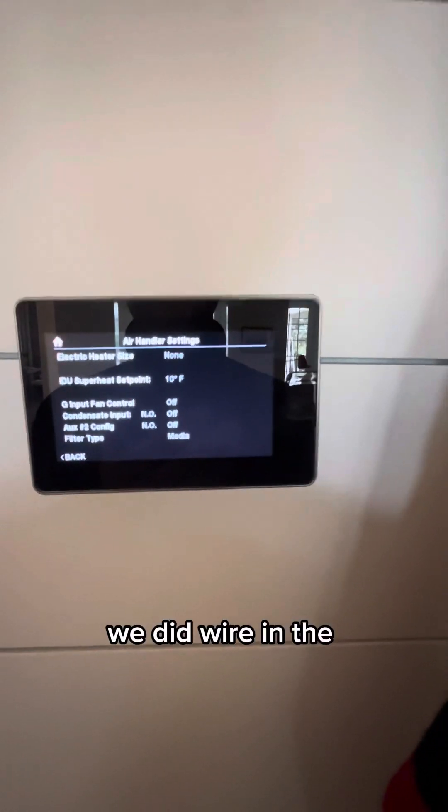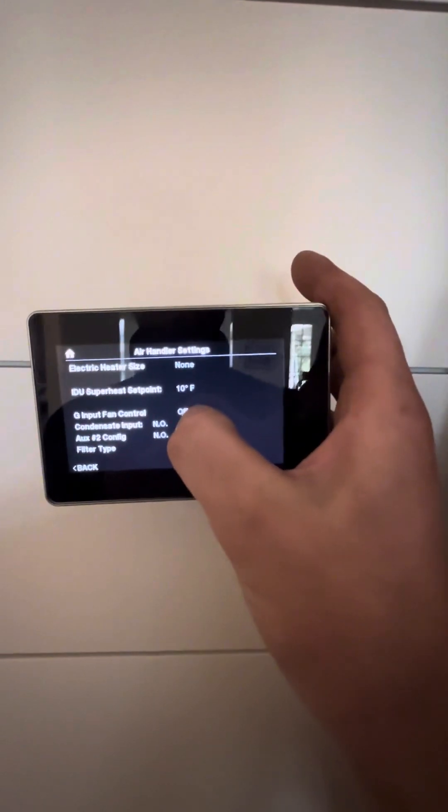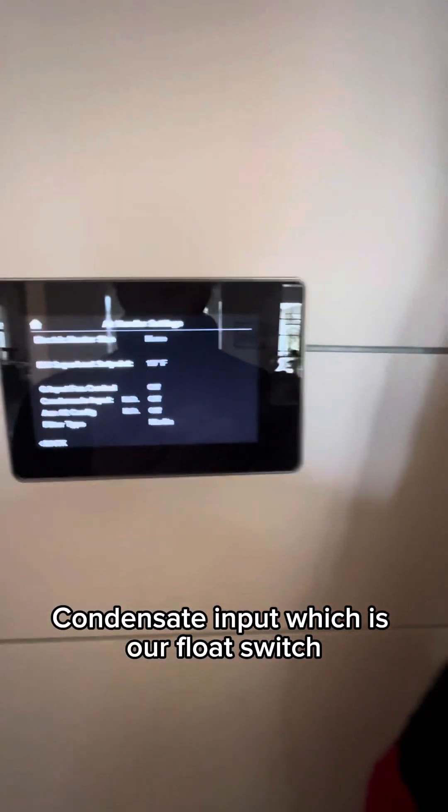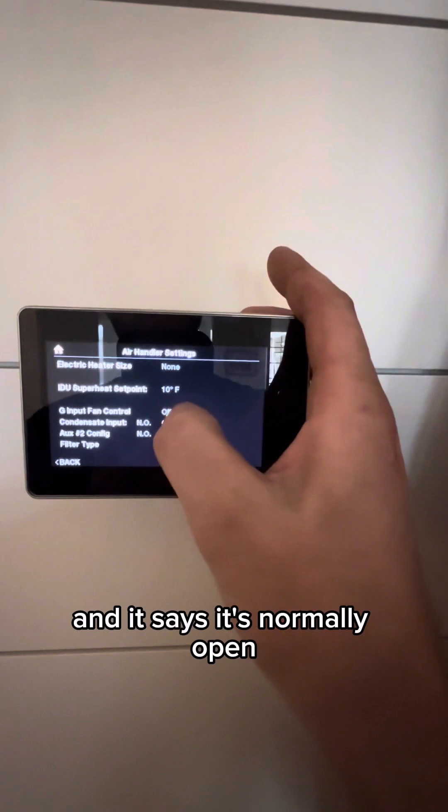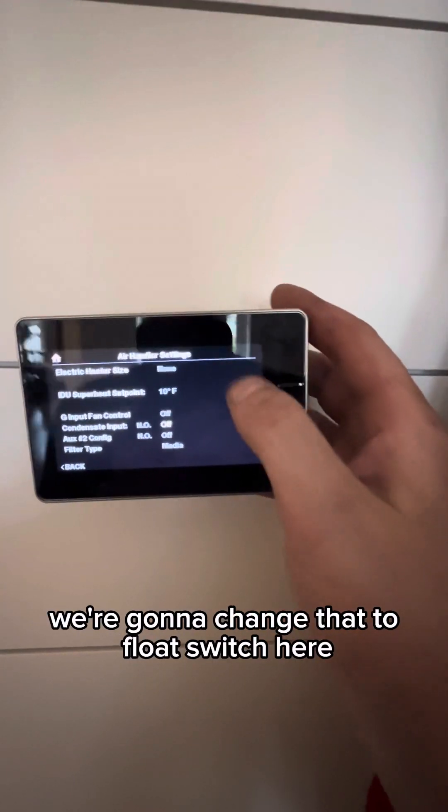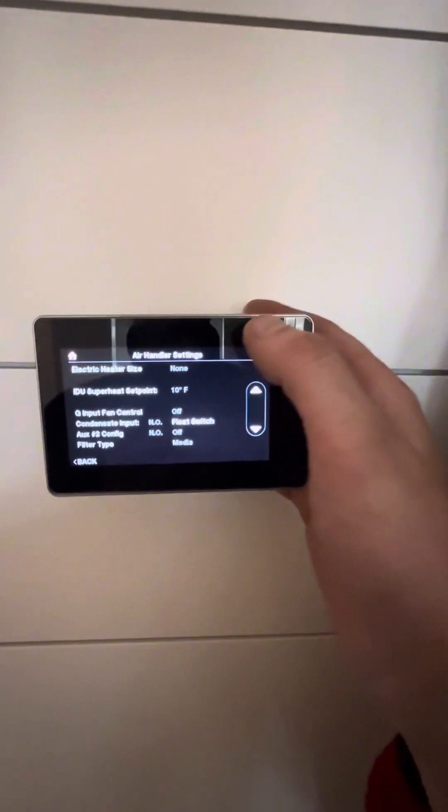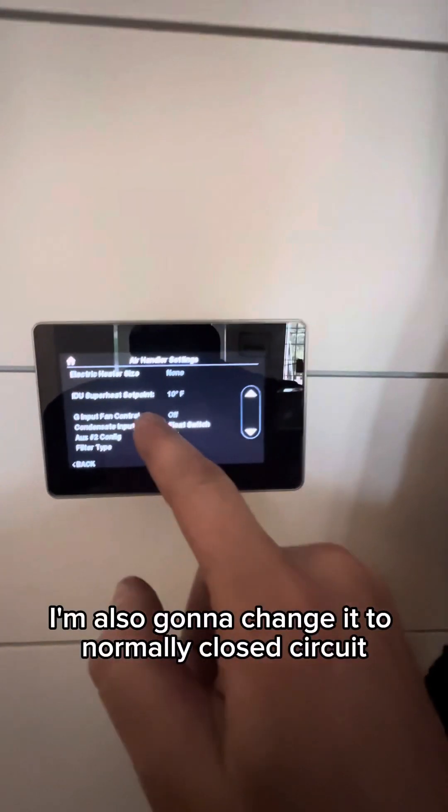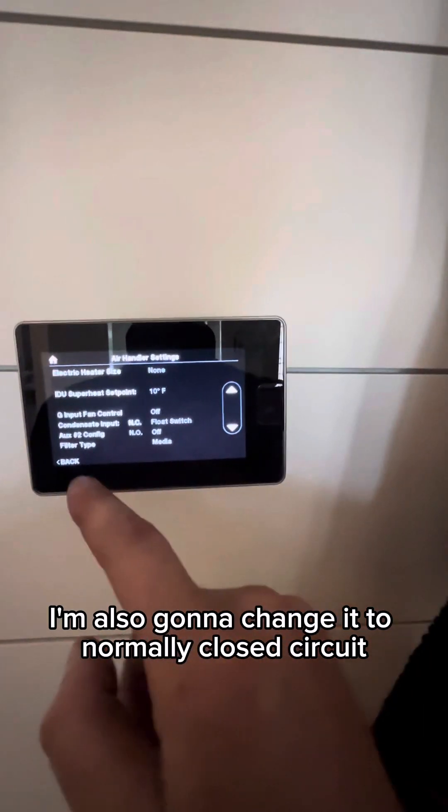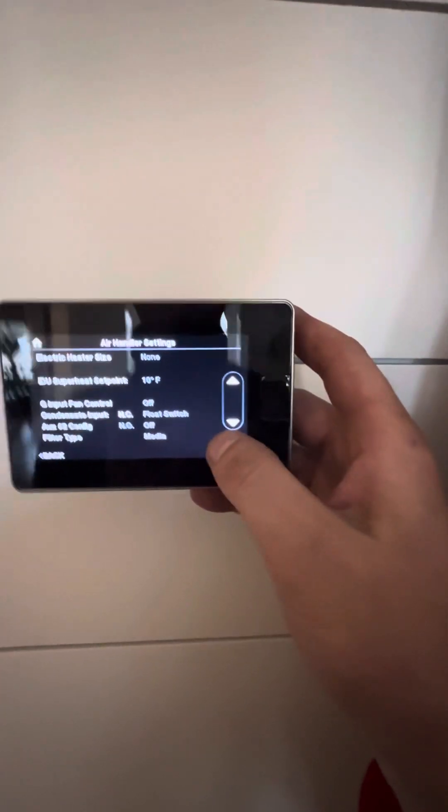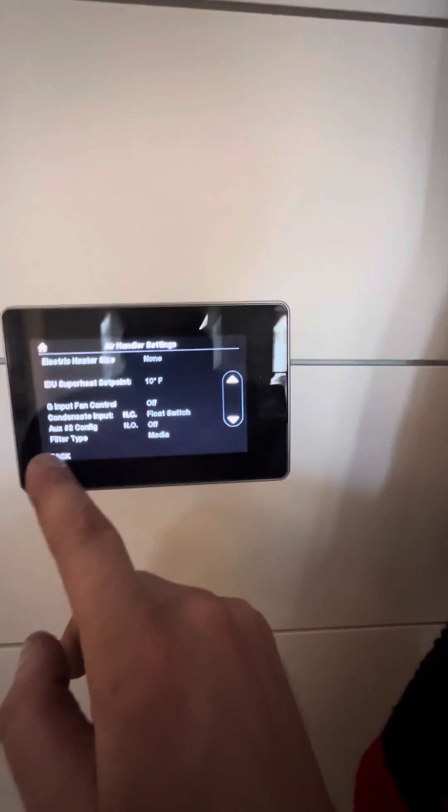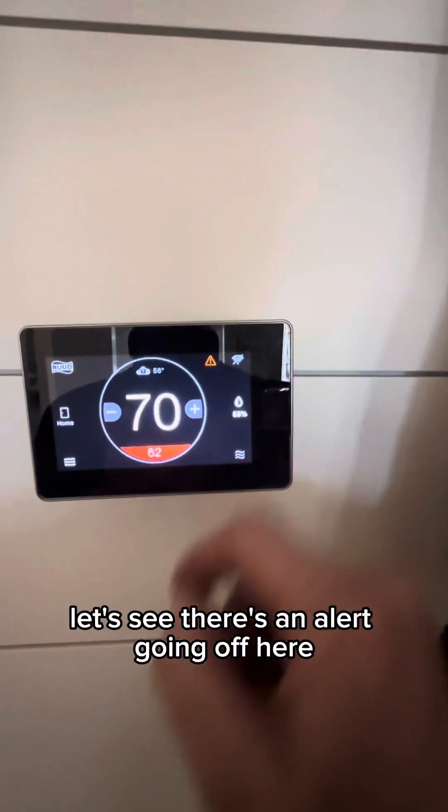This is just the general settings. We did wire in the condensate input, which is our float switch. And it says it's normally open. We're going to change that to float switch here. We're also going to change it to normally closed circuit.